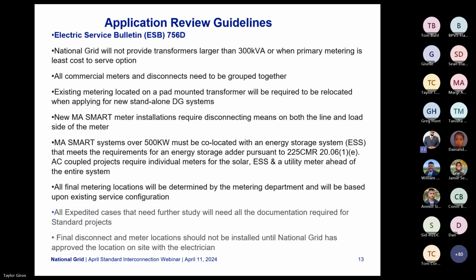These are just some of the guidelines for when we look at submissions that it's good to know, including how we won't provide 300 kVA, anything larger than a 300 kVA transformer for standalone storage. All commercial meters and disconnects need to be grouped together. Any existing metering located on a pad transformer will be required to be relocated for any new standalone system. Smart meter installations require disconnecting means on both the line and load side for any self-contained 480 volt systems.